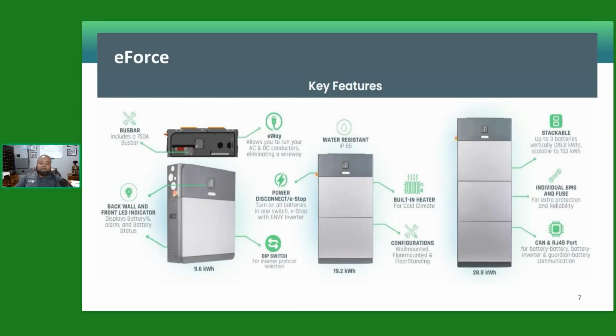The system is built to cover the entire US and Canada, which means it has self-heating capability. Regardless of how cold it is, with our LFP chemistry, if it's too cold—under 32 degrees—the battery will discharge but not recharge. Because of the self-heating capability, it will warm itself up so that in the colder months, the battery will recharge and then discharge as the customer calls for power.